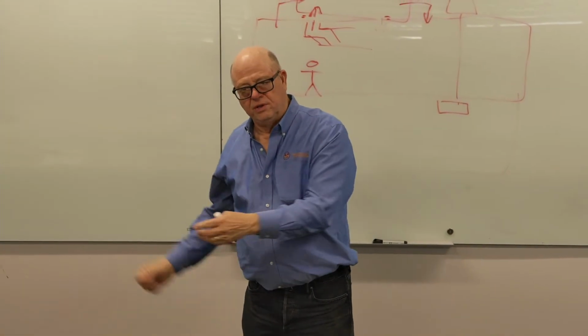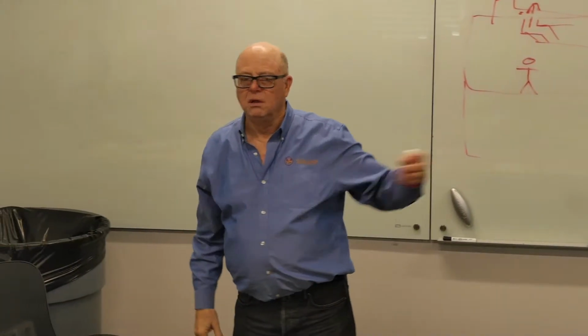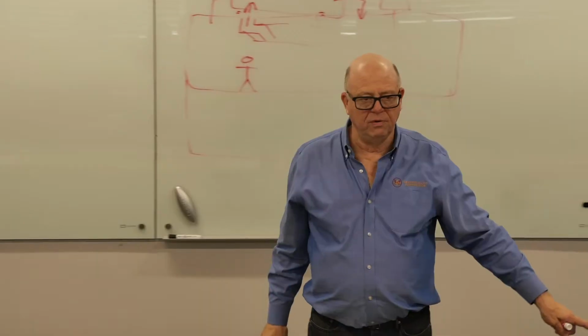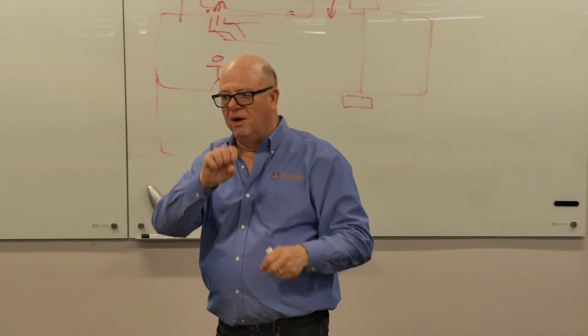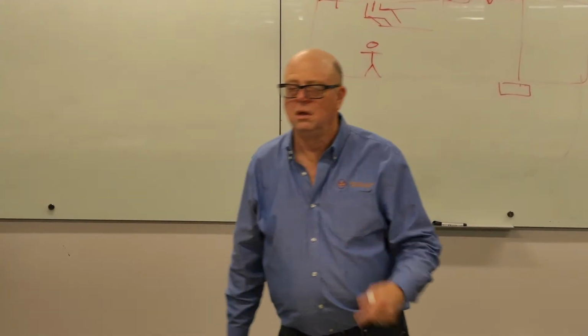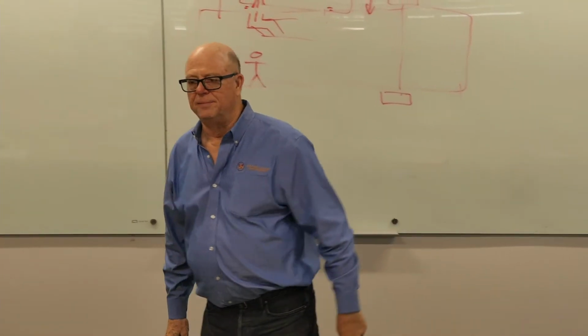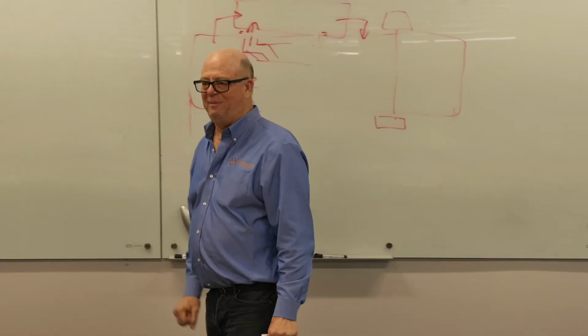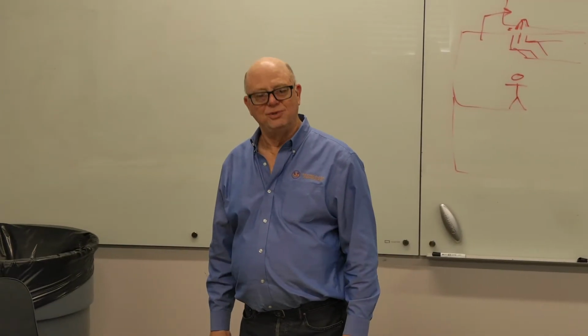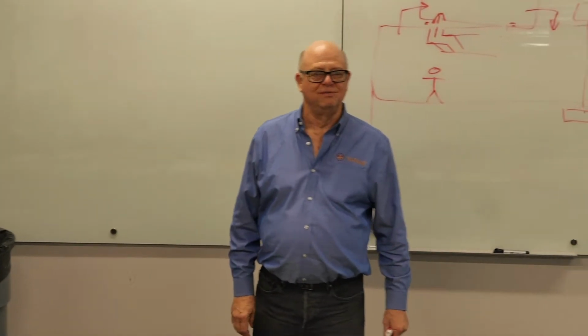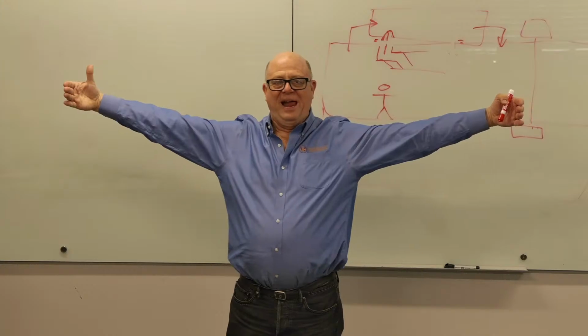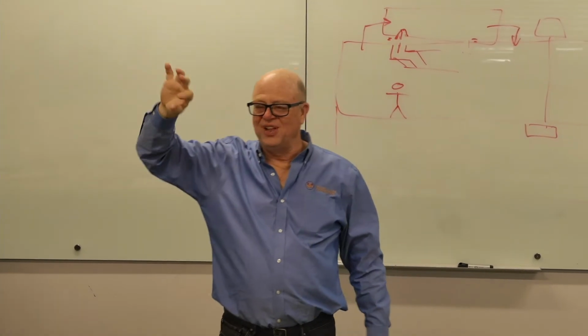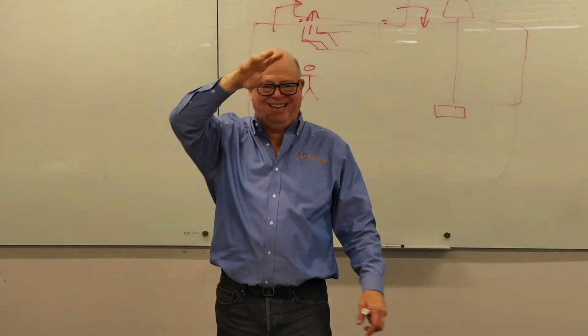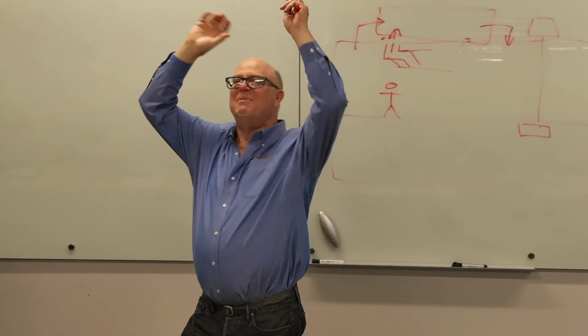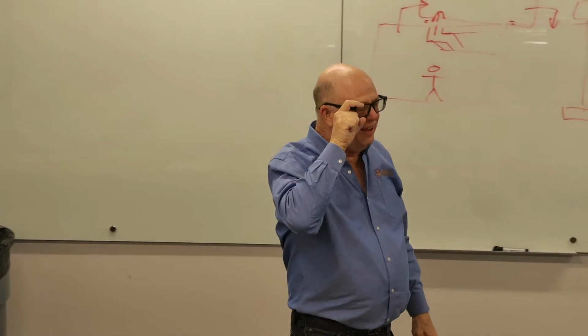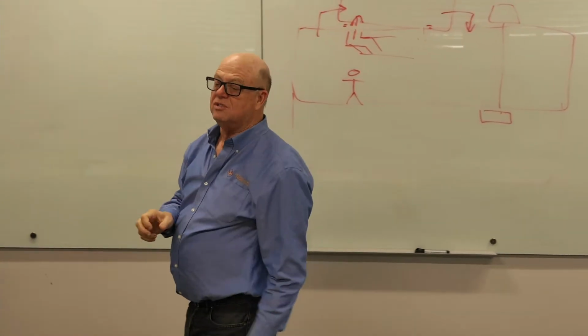But in this studio environment, they couldn't be hearing the server room, because you guys have all heard, you get enough of those little muffin fans going and it's pretty audible. So we put a sound boot on it. But we had to get it right the first time. So we were conservative. Our sound boot was about this long, 10 feet long, low velocity. I think there were at least 3 elbows, 4 or 5 elbows, actually. By the time we stuck it up on there, they were able to run this exhaust fan, ECM motor.